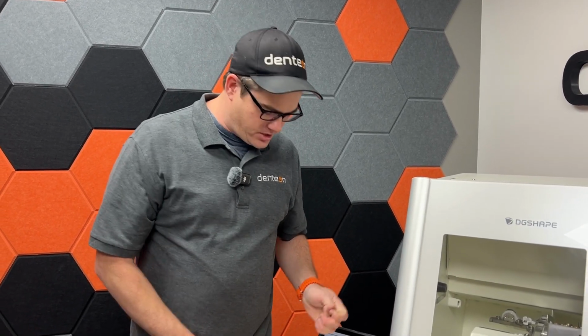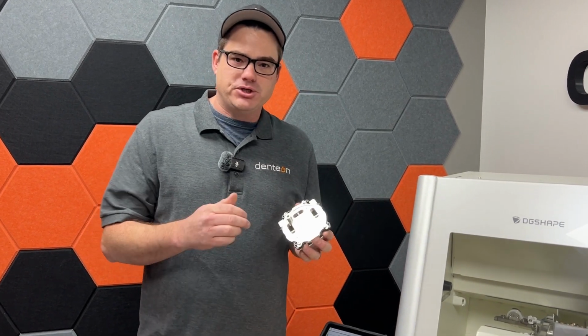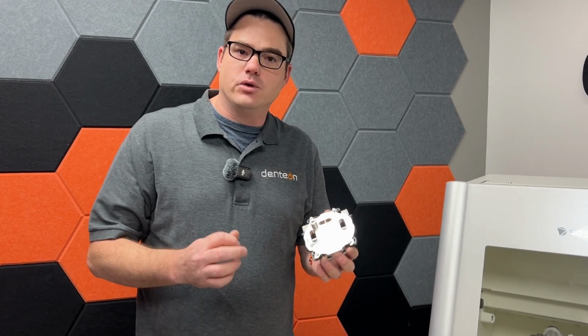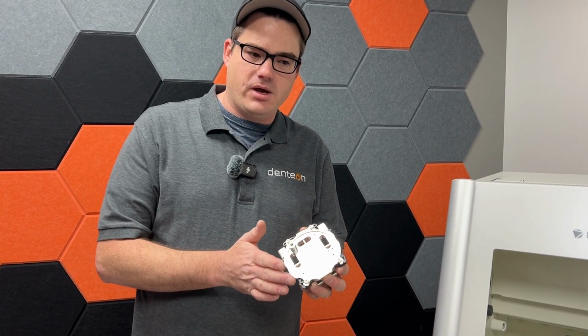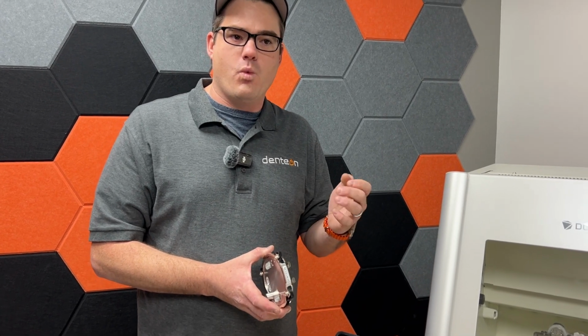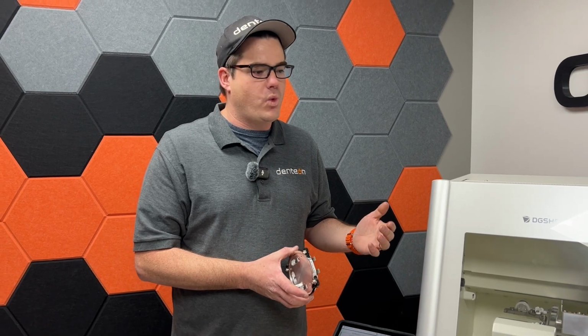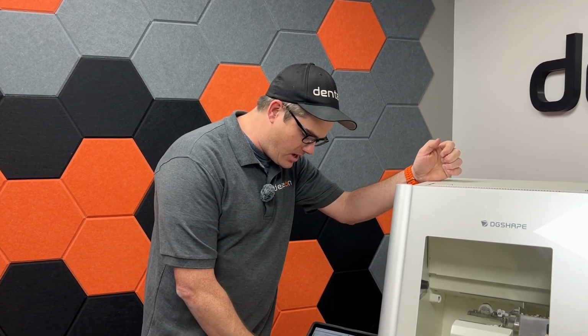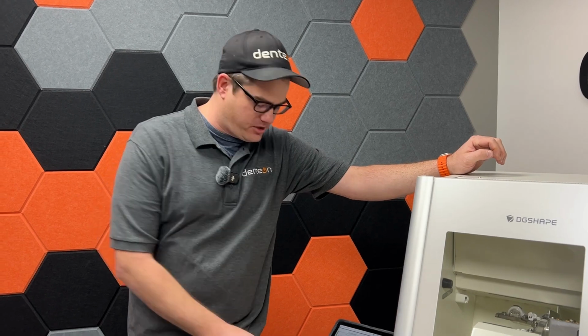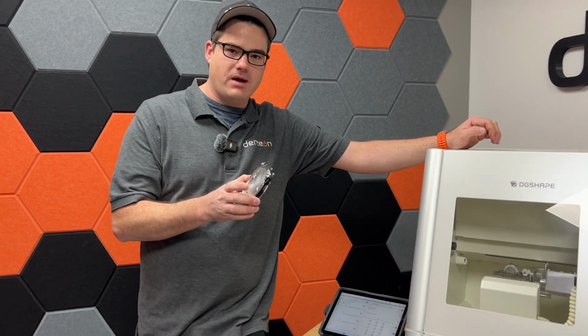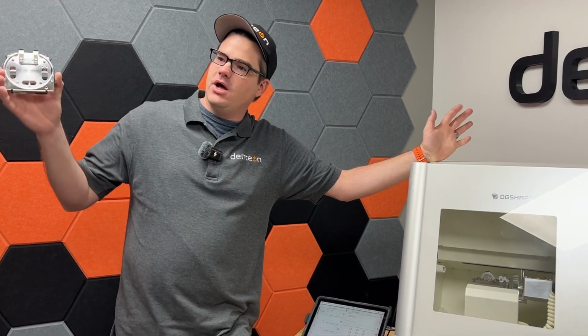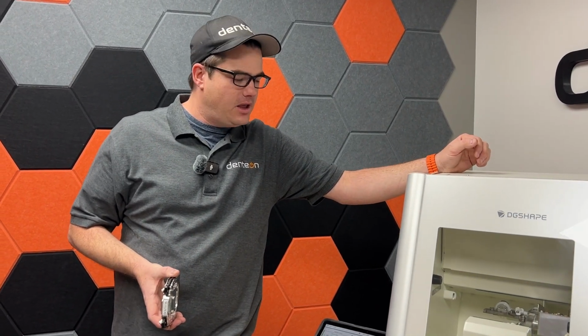And so what a calibration does is it allows the machine to measure itself systematically to reset 0. So now we're going to offset any of those changes that may have occurred over time and be able to compensate for that. So that's what you're doing with a calibration. And so the question is, when are you supposed to calibrate? And the issue is that it's possible to get a bad calibration, especially if you calibrate with a dirty object, or the planets are aligned in an unfavorable way.